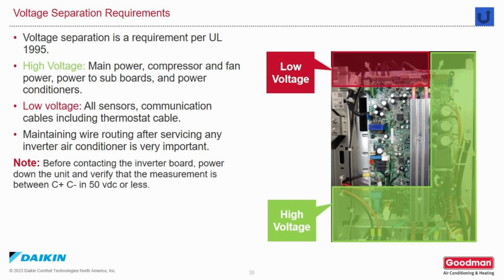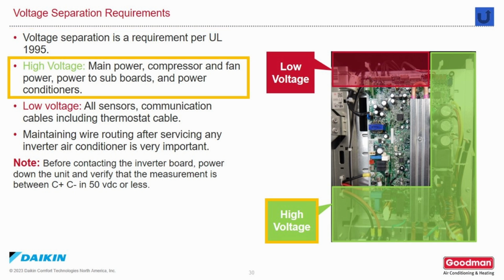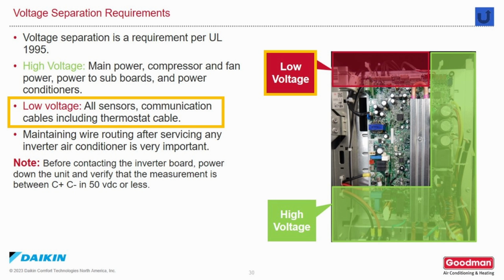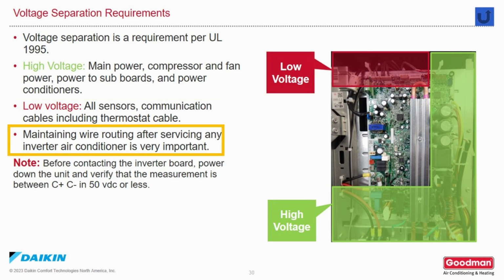Inverter-driven equipment carries different voltages on the control board than does standard equipment. Inverter smoothing capacitors could hold up to 370 volts DC. Therefore, voltage separation is required per UL 1995 standard. The green section that you see here is a high voltage. High voltage could be AC or DC. Main power, compressor and fan power, power to the subboards, power conditioners, anything that would be dangerous to the technician. The red section that you see here is low voltage, such as communication cables, all your sensors such as thermistors and pressure switches, and even thermostat connections. For technician safety, these things must be separated on the control boards.